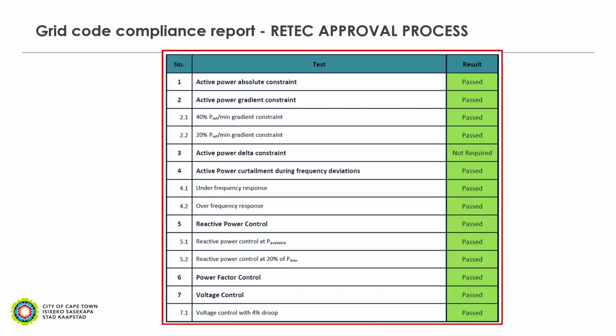And then typically the customers do what we call a grid code compliance report, which is part of the RETEC approval process. And this is typically a summary of that report where, in terms of the grid code, they need to comply with these various aspects: the active power constraints, the active power gradients, the active power delta, the curtailment, the reactive power control, the power factor control, and voltage control, with all those percentages. And in this case, after a test, they would indicate if it passed or if it is maybe not relevant to the particular plant. This dry run test report with the detail gets submitted to RETEC, which is the NERSA branch responsible for the approvals of the category B systems.